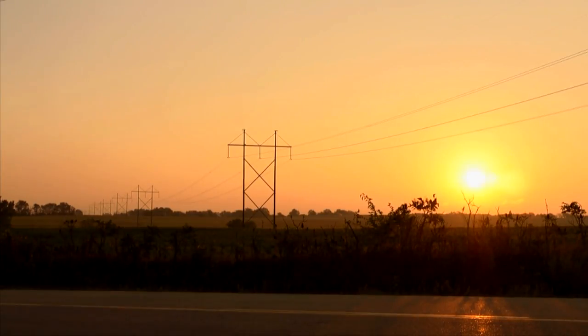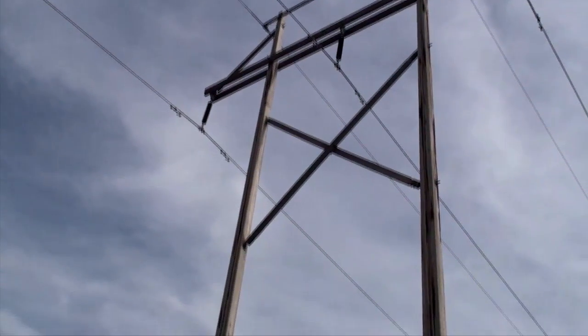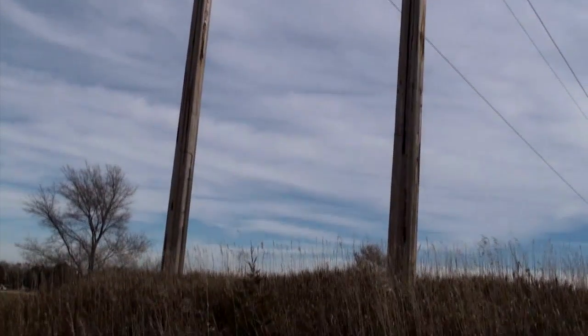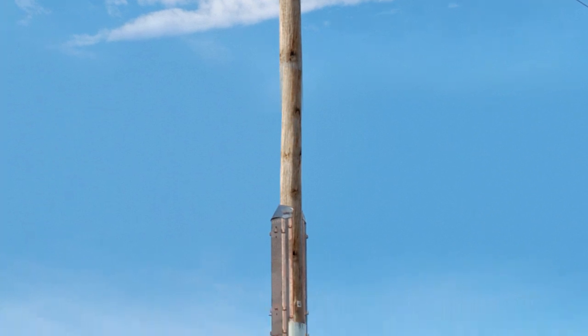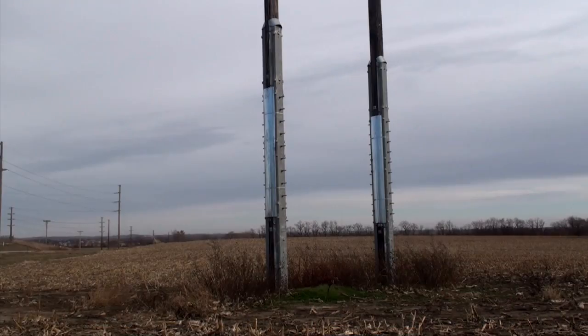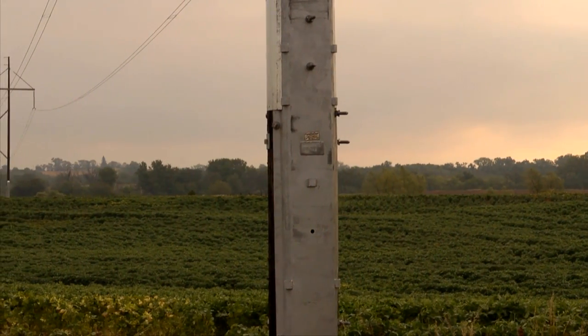Not all structures can be raised. Guyed angle and dead end structures should not be raised using the Phase Razor system. When it becomes necessary to change out a structure, LWS can supply engineered wood structures in just six to eight weeks after drawing approval. Single pole structures have been raised using the PRHR Reinforce and Raise Phase Razor units. The average age of the thousands of structures that have been raised is 50 or more years. Generally speaking, if a structure is good enough to remain in service, it's good enough to raise.